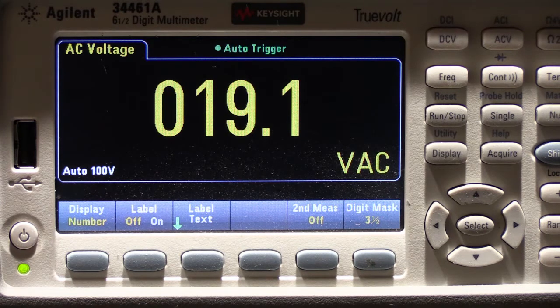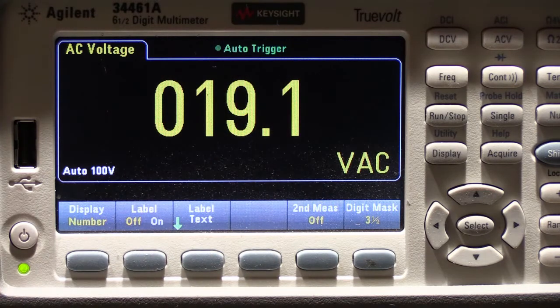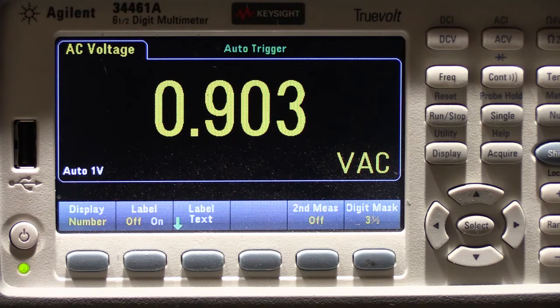I guess what I'm going to do is show you that the fuse actually works. I'm still measuring the secondary output, and I'm going to take my screwdriver and short across the screws to blow the fuse, on purpose. How about that? Here we go - 1, 2, oops, it got stuck. 1, 2, 3, short circuit - 0.9 volts. So we blew the fuse inside the transformer, and essentially we're right back to where we started.